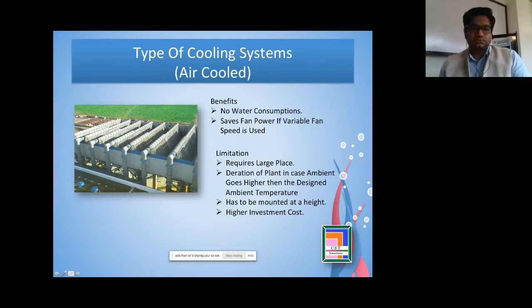So, types of cooling tower. Let's discuss the air cooled first. The benefits of air cooled condensers are that there is no water consumption, and fan power is saved if variable fan speed is used. That means if we install a VFD, a variable frequency drive, on the fans, we get a reduction of the air volume, and it ultimately saves power at low ambient temperature. The limitations are that it requires a large area, and derating of the plant in case ambient goes higher than the designed ambient temperature.